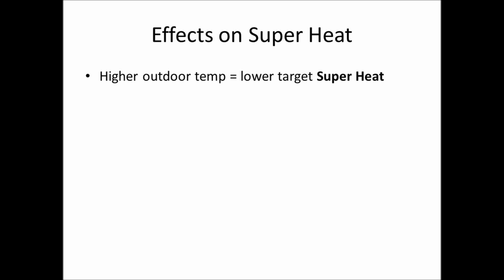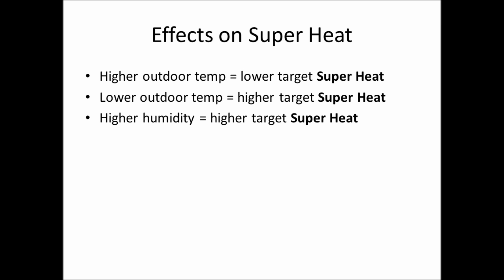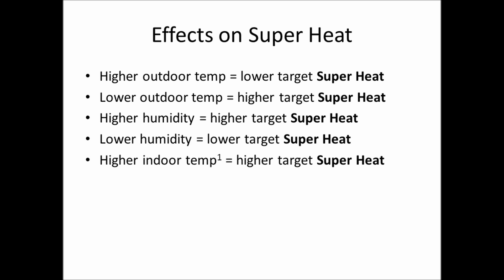Let's look at the effects on superheat. A higher outdoor temperature will give you a lower target superheat, and a lower outdoor temperature will give you a higher superheat. A higher humidity gives you a higher superheat, and a lower humidity gives you a lower superheat. A higher indoor room temperature gives you a higher superheat, and a lower indoor temperature gives you a lower superheat.